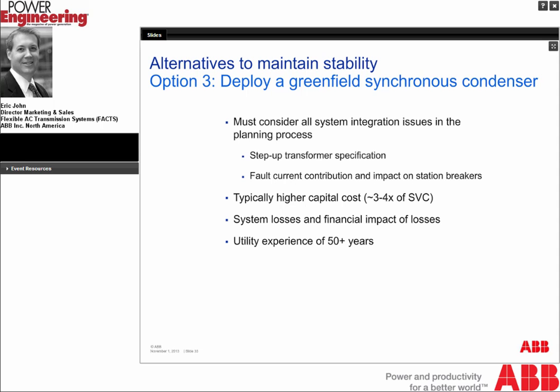A Greenfield synchronous condenser, we've seen in the market that they have a higher capital cost, running 3 to 4 times the cost of an SVC. That's on a turnkey kind of basis. And this is based on our observations in the marketplace. Again, the losses and the financial impact of the losses should be evaluated. And again, introducing a fairly high loss device into the system can have consequences. And synchronous condensers have been around for a long time, 50 plus years, and I would say they're very much a tried and true kind of hardware for providing dynamic reactive support.